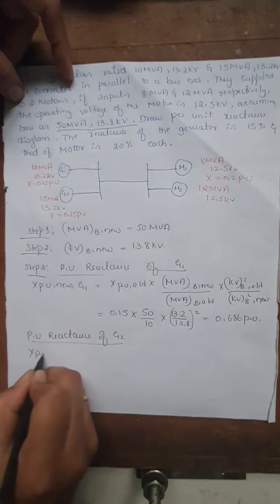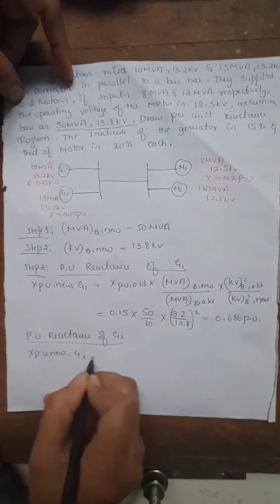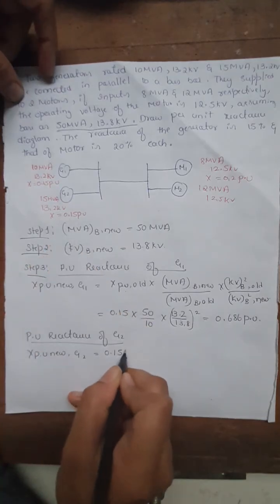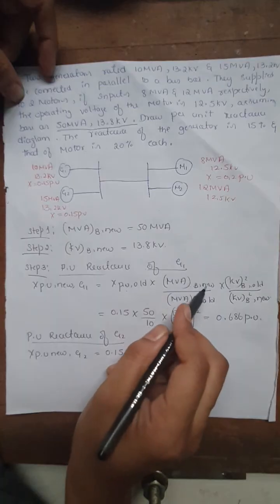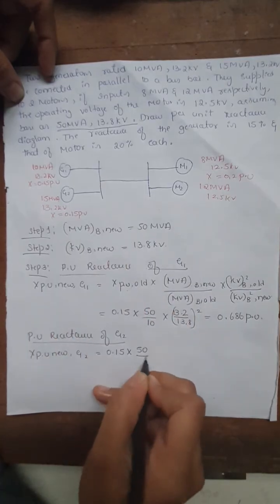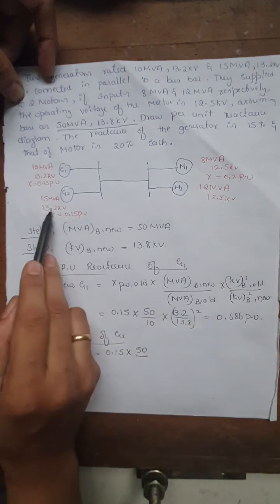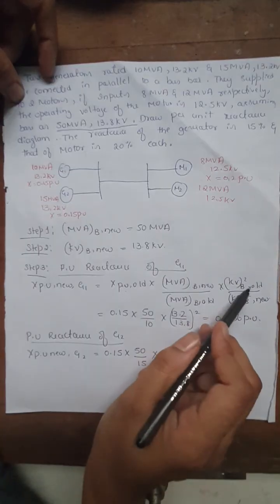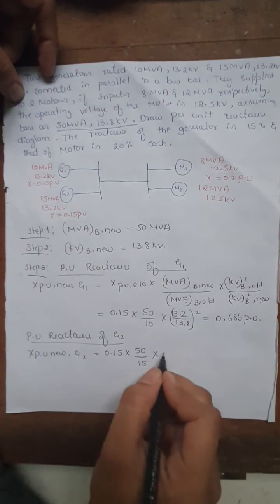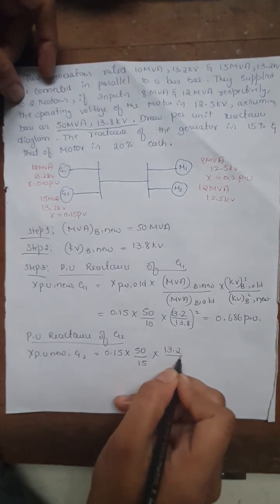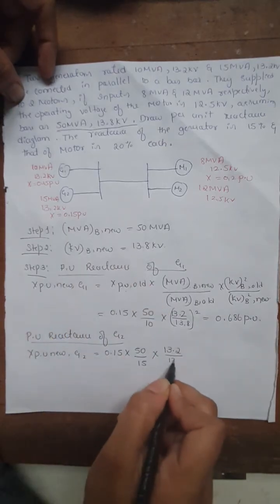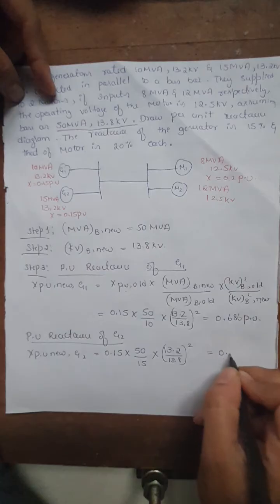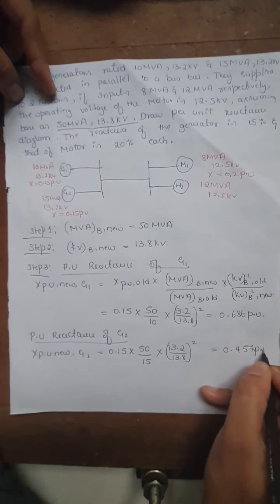For generator 2, using the same formula: X(pu, new) = 0.15 × (50 / 15) × (13.2 / 13.8)² = 0.457 per unit. The old MVA base is 15 MVA, the old kV base is 13.2 kV, and the new kV base from step 2 is 13.8 kV.